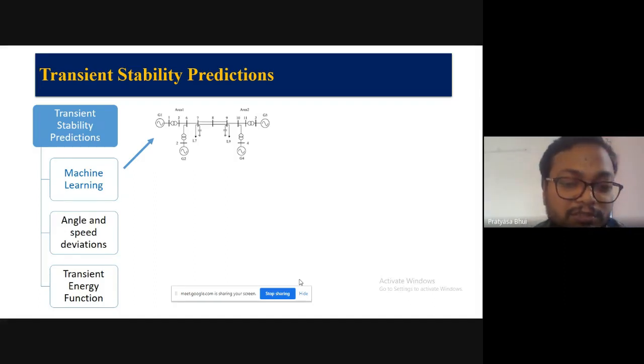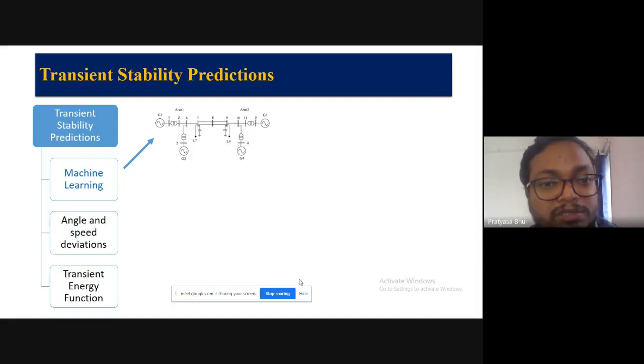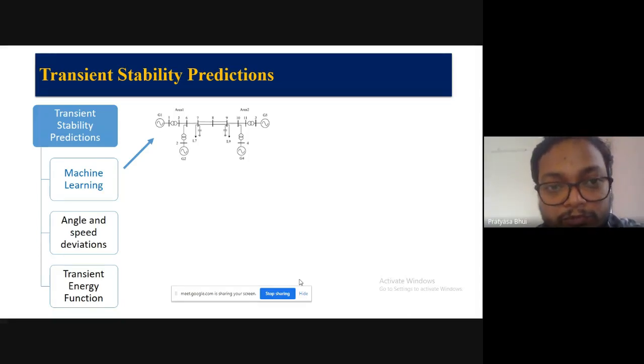You might know that the Indian government is planning to install synchrophasors, or has already installed them at some places. The Indian government is installing PMUs at all high voltage buses, 230 kV or 400 kV buses. They will send the phasor measurements from those buses: voltage measurements, angle measurements, frequency measurements, active power flow, reactive power flow. Those measurements will be sent to a control center. All those measurements will be time synchronized, and sent 25 to 50 times in a second.